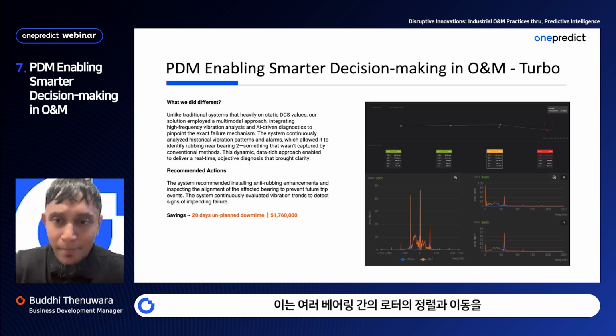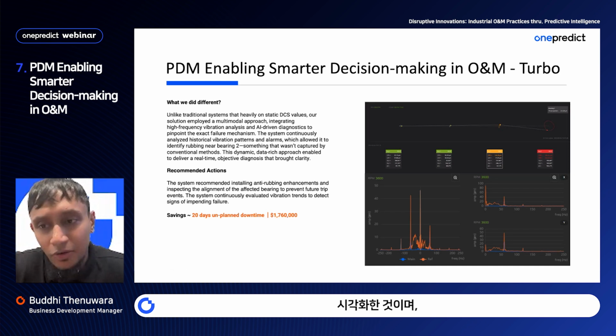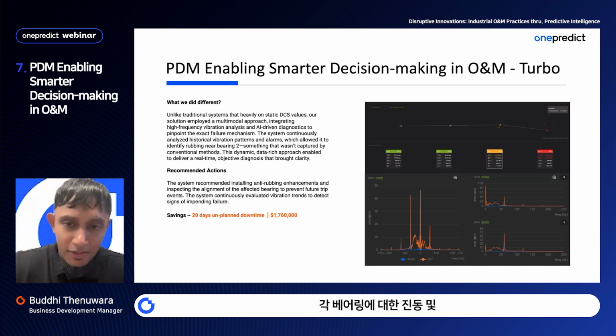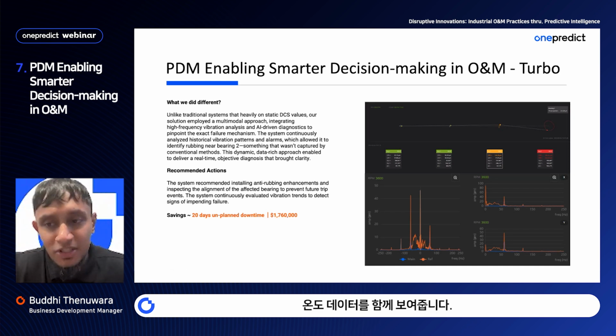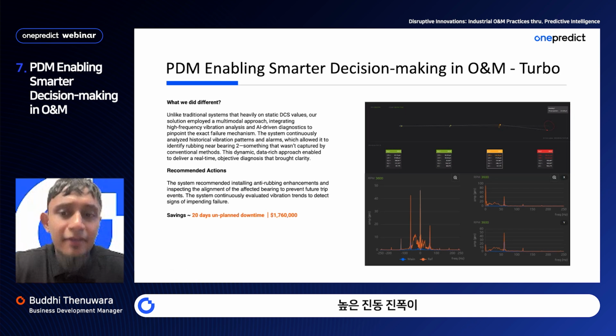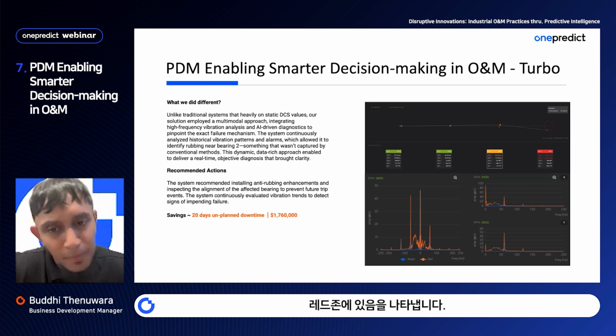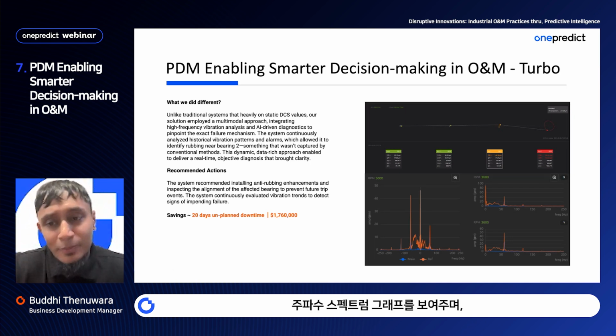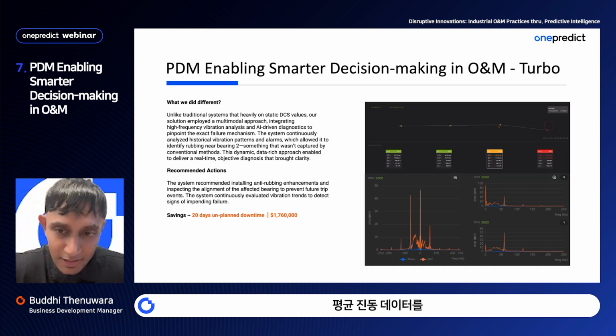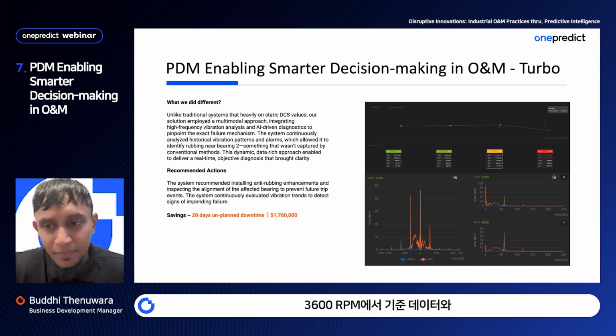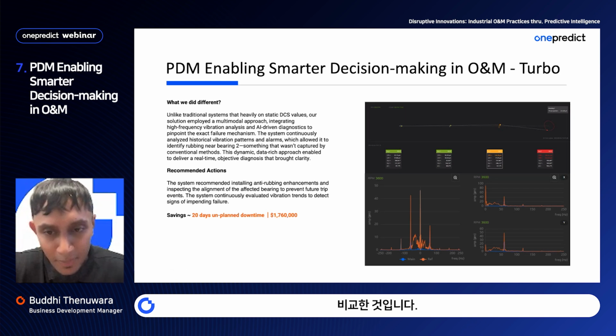visualizing the alignment and movement of the rotor across various bearings, with corresponding vibration and temperature data for each bearing. Anomalous behavior is detected near bearing 4, indicating a high vibration amplitude in the red zone. The second image displays frequency spectrum graphs, comparing the main vibration data against reference data at 3600 RPM.